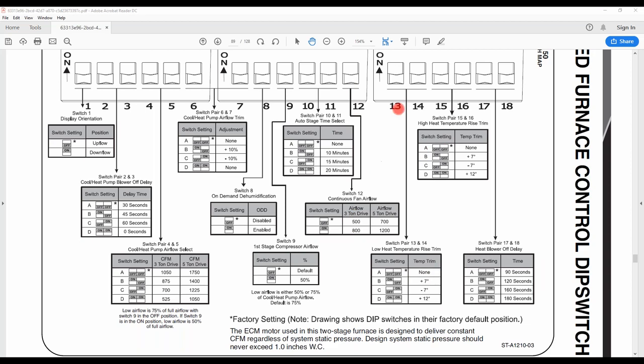If you take switch number 13 and turn it to the on position and leave 14 off, you are going to slow your airflow down, which will increase your temperature rise by approximately 7 degrees. Almost every time I go to a job site, I recommend going to that plus 7 degrees, or slowing your airflow down a little bit, getting a higher temperature rise, as long as we are within the specifications of the temperature rise for that actual model. Typically, a homeowner is a little bit more happy with that increase of 7 degrees.